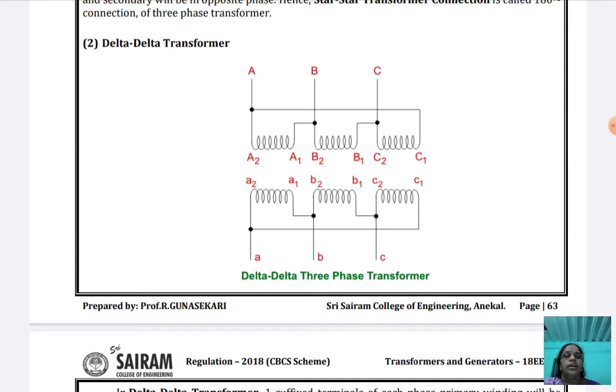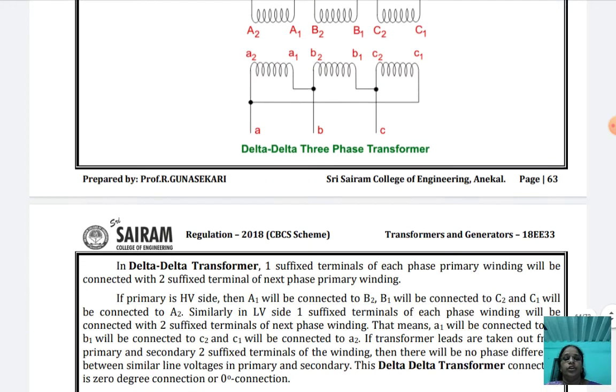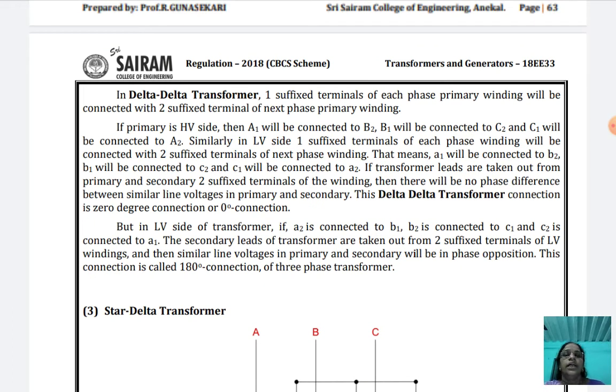Similarly, on the LV side also, the small letters represent the LV side. So how to make a delta connection? The starting end of one phase is connected to the finishing end of the next phase. Like that you can make a delta connection. In the delta connection, the suffix 1 terminal of each phase of the primary winding is connected with the suffix 2 terminal of the next phase of the primary winding. In this case there is no phase difference between the similar line voltages in the primary and secondary, because this delta transformer connection is a 0 degree connection only.